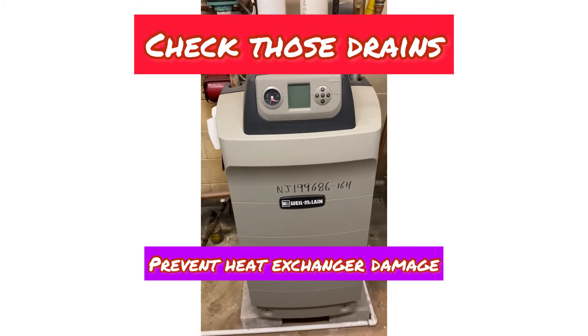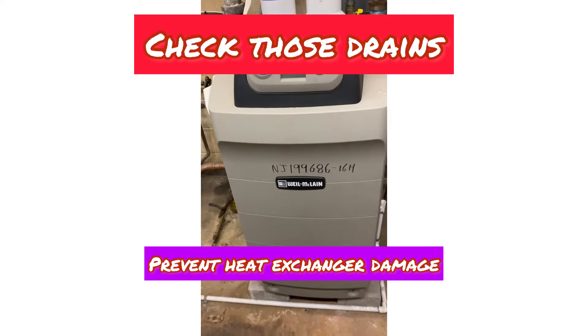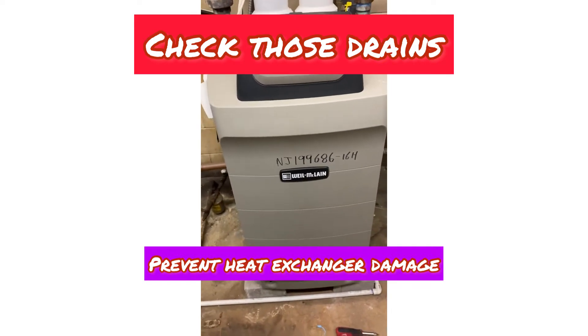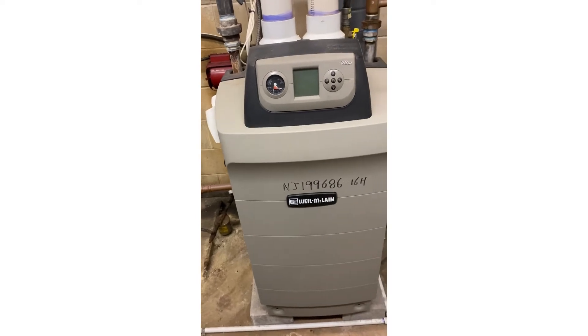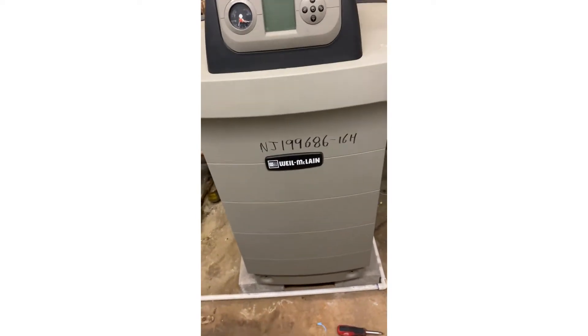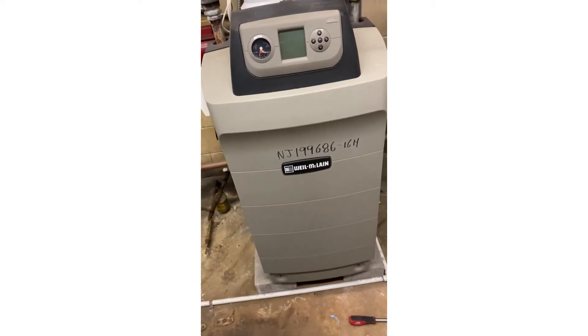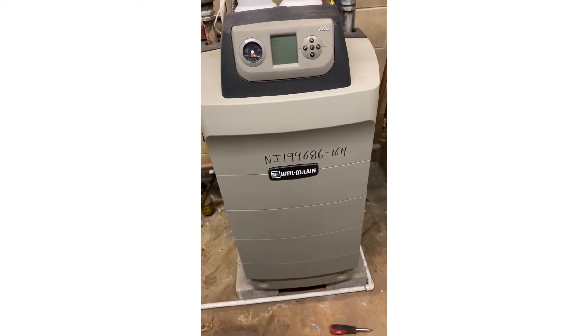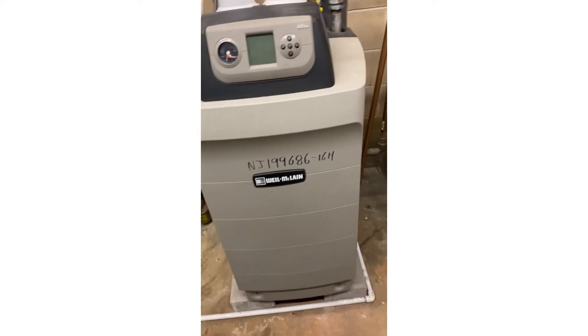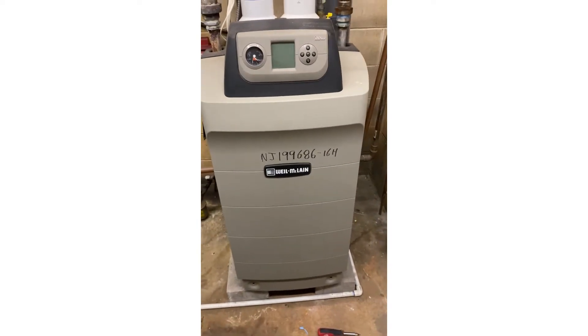Weil-McLain Ultra boiler — already opened this up and I know what's going on here. When you service these units you definitely want to make sure you check that condensate drain, because if you don't, eventually it'll back up and rot out your heat exchanger, and then you're in for a big repair. Let me set this down and get the cover off.